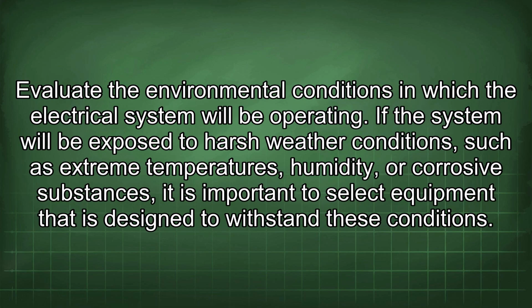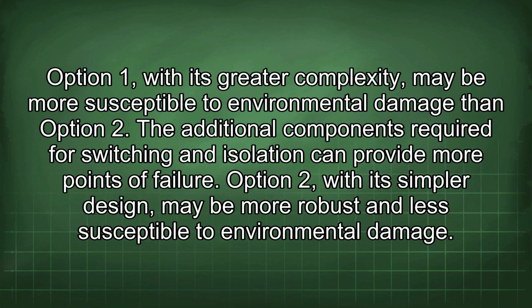Evaluate the environmental conditions in which the electrical system will be operating. If the system will be exposed to harsh weather conditions such as extreme temperatures, humidity, or corrosive substances, it is important to select equipment that is designed to withstand these conditions. Option 1, with its greater complexity, may be more susceptible to environmental damage than option 2. The additional components required for switching and isolation can provide more points of failure. Option 2, with a simpler design, may be more robust and less susceptible to environmental damage.